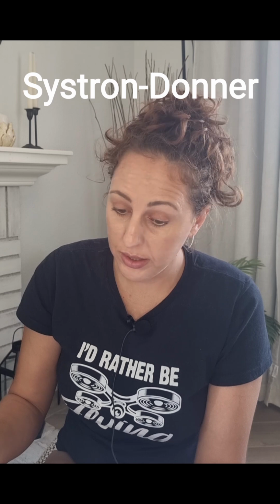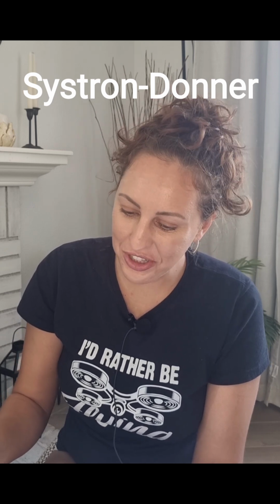Question: after a fire is extinguished or overheat conditions removed in an aircraft equipped with a Systron Donner fire detector, the detection system, answer, automatically resets. Note, when a fire that has been detected by the Systron Donner pneumatic fire detection unit is extinguished and the temperature drops, the hydrogen gas that had been released inside the detection unit is reabsorbed and the pressure in the tube is reduced. This opens the pneumatic switch and the system returns to normal, ready to signal another fire or overheat condition.